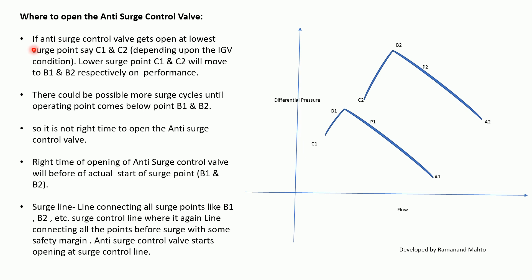Where should the anti-surge control valve open? If it opens at the lowest surge point — say C1 and C2 depending on IGV condition — those points will move to B1 and B2 respectively on the performance curve. By opening the anti-surge valve, the operating point tries to move from C1 to B1. However, there could be multiple surge cycles before the operating point comes below B1 and B2, since the area between C1/C2 and B1/B2 is still within the surge zone.